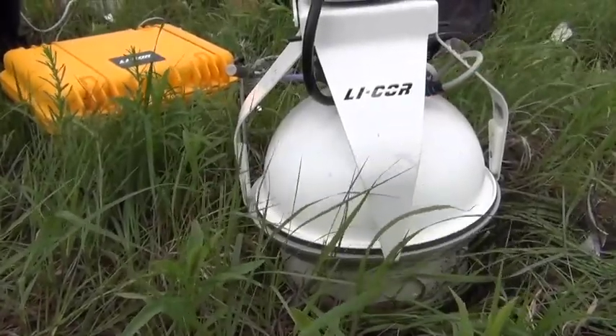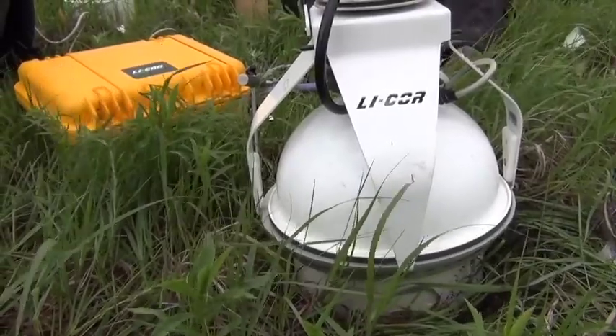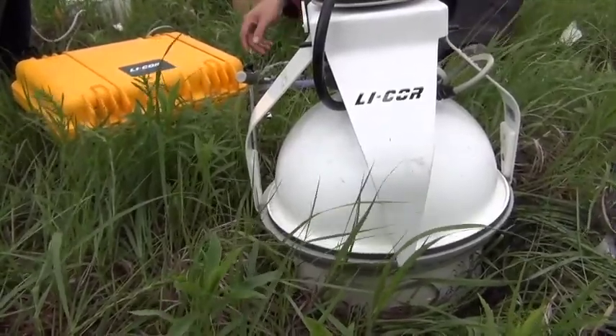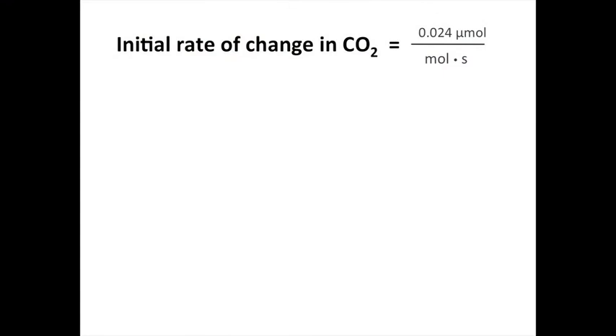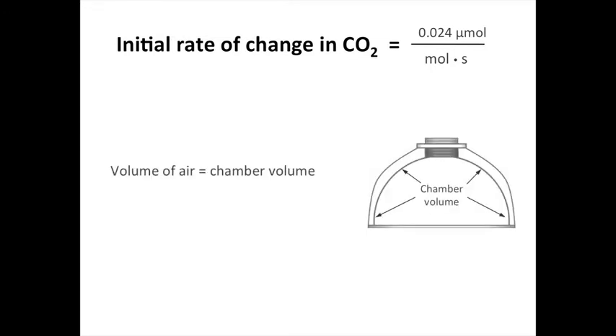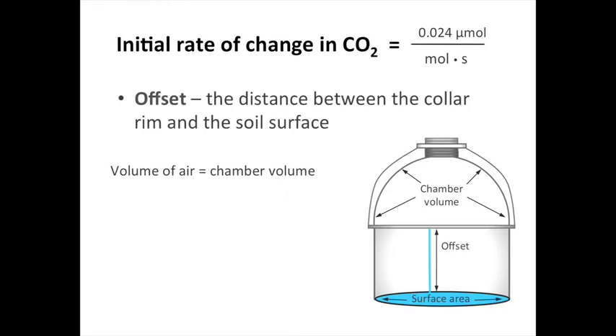Now that we've got a measurement of CO2 from our instrument, what do we do with it? The instrument is calculating the rate of change in CO2 as a mole fraction, like this. When it does this, it assumes that the volume of air we are measuring is the same as the volume of the chamber, but we have that extra space created by the collar that we have to account for. Remember when we measured the surface area and offset of our collars? We'll use those measurements now to calculate the volume of the collar and then our total volume of air.